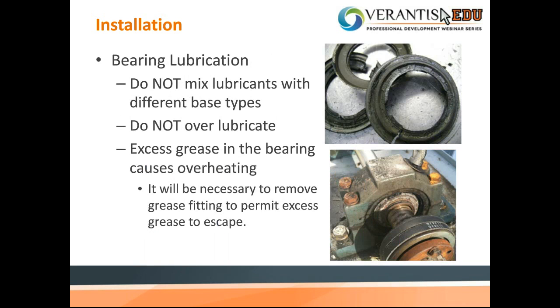So this next line about bearing lubrication, this is very, very, very important. Do not mix the different types of lubricant that are required. They have different bases, and it is not a homogeneous mixture. A lithium grease will not blend with a polyurea base, and there are charts online. There's a bunch of different material compatibility lists available. So if you're using a type of grease that we're not discussing here, by all means, check out your material compatibility lists and see what you can mix with it.